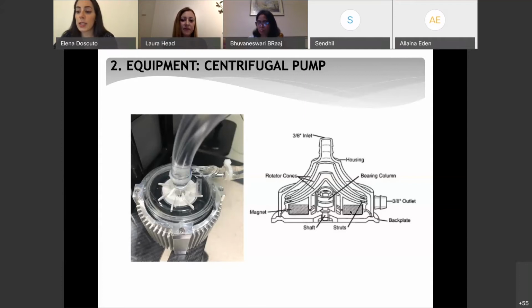And this magnetic coupling means that the speed of the driver magnet inside the console equals the rotational speed in the pump. So when the impeller rotates, it generates a pressure difference. So you get negative pressure, which is draining the patient here, and then positive pressure, like expelling the blood of the patient, and that's what creates flow.